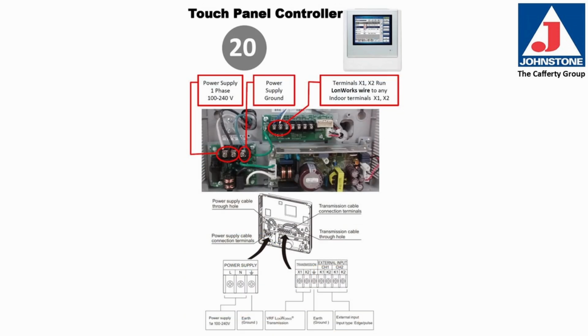Here are the wiring connections on a touch panel controller. You'll see the power supply, which is 100 to 240 volt single-phase AC, and the power supply ground. Terminals X1, X2 run LonWorks wire to any indoor unit terminals X1, X2. Here is the location of the power supply connection terminals. Here are the connection terminals for the LonWorks connection X1, X2, and Shield, and the external input channel 1, K1, K2, and channel 2, K1, K2.